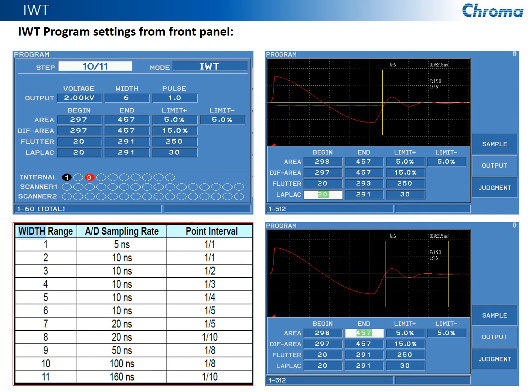We can even do a pulse that has no judgment prior to doing the pulse that we would do for a judgment test. Down here you can see we can set the beginning and end on each of the different types of tests we perform. And the beginning and end is what you see here with the cursors. It determines what portion of the waveform we're going to use when we're testing that particular device. So we can also change that, like I mentioned, for each one of these four different types of measurements and judgments.